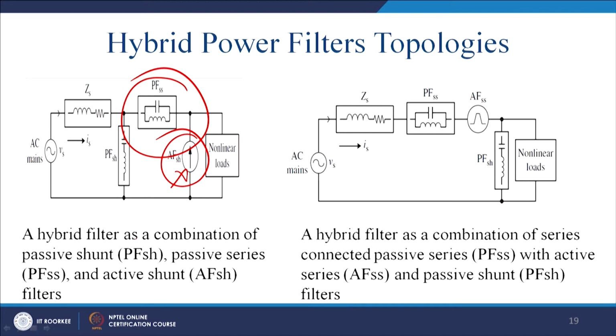The hybrid filter is a combination of the passive shunt, passive series and active shunt filters. Same way, you can have the cleaning up operation in the series part. Mostly it will clean up the voltage, and thereafter whatever remains will be sunk into the shunt component. The hybrid filter is a combination of the series connected passive series with the active series and the passive shunt filter.